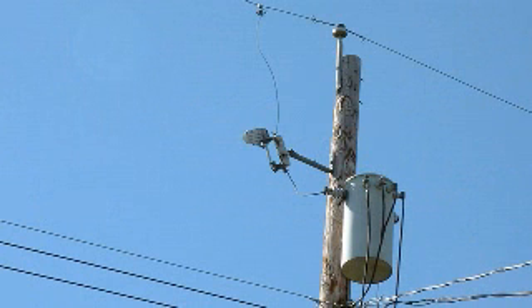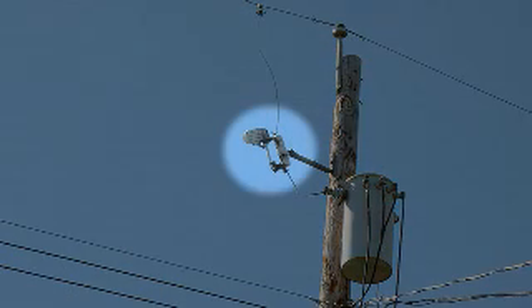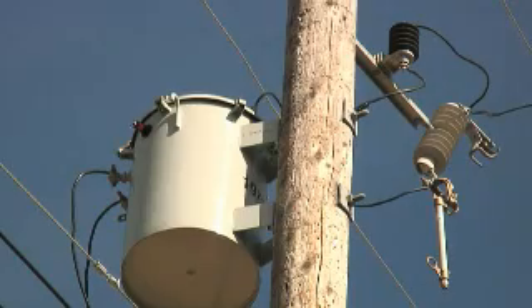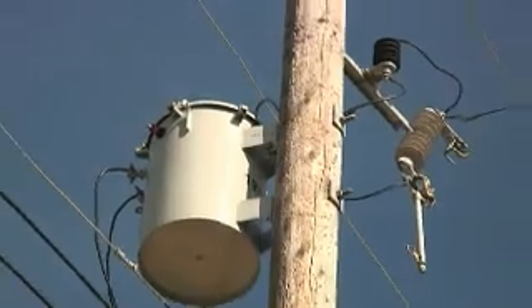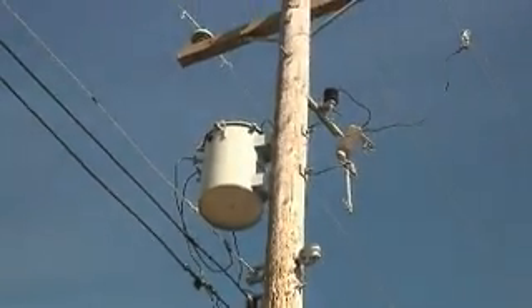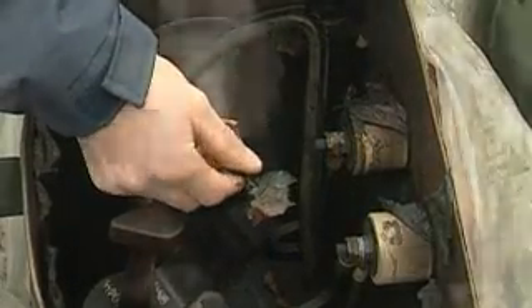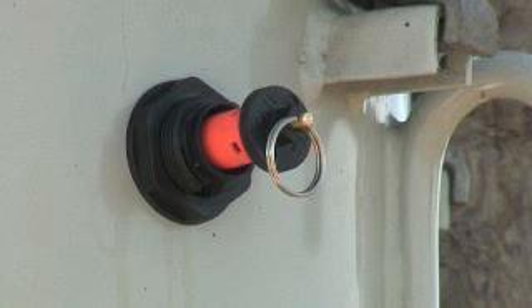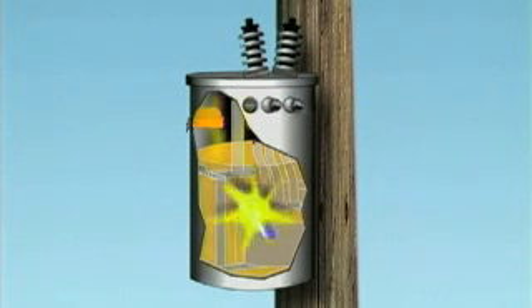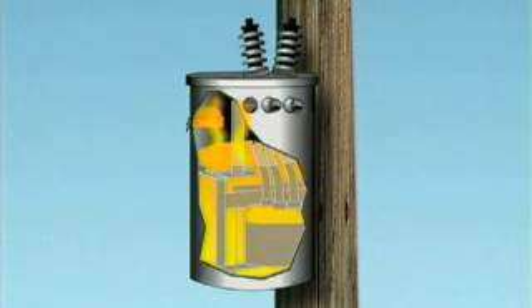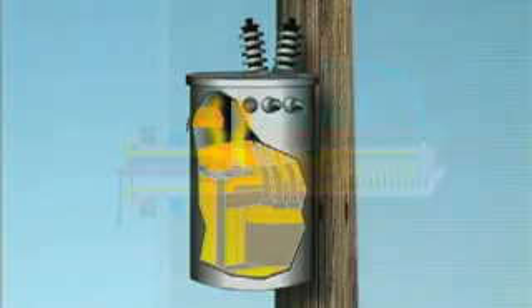Pole-top transformers are usually connected to the primary supply network by a cutout fuse. The cutout fuse will operate when there are fault currents from the distribution network or evolving faults within the transformer. If these overloads result in permanent damage to the transformer's internal components, an internal fault has occurred. A fault can produce several types of gases that, when mixed in particular proportions, can become explosive.